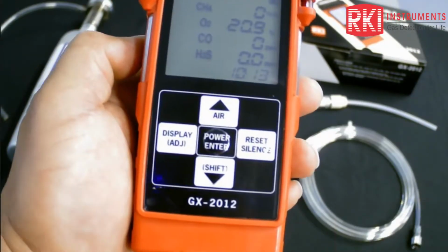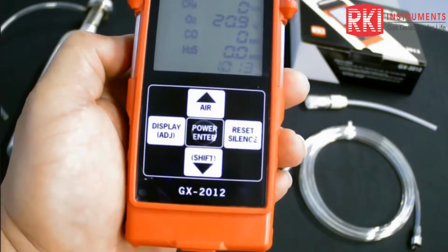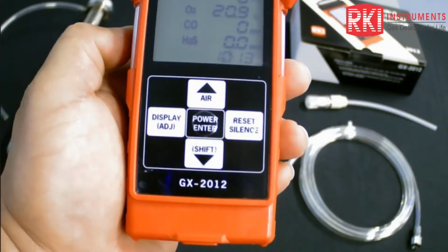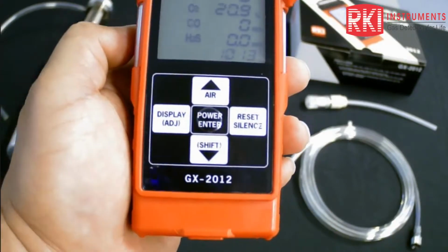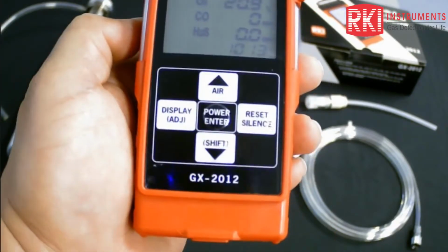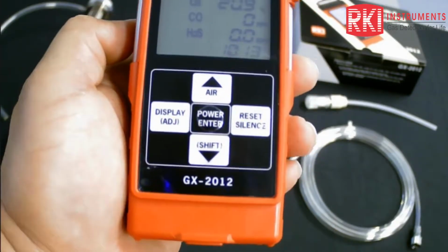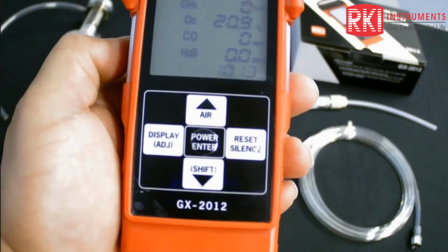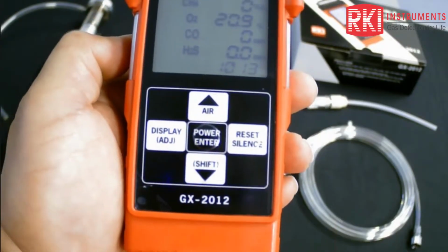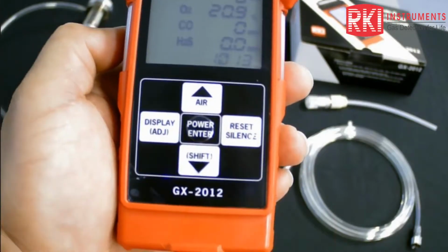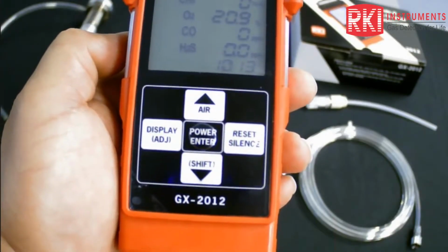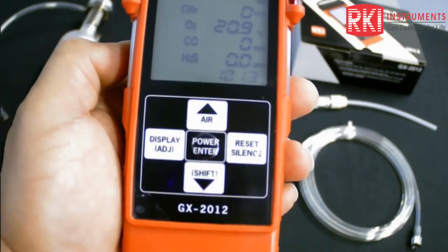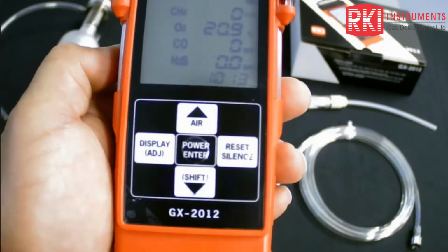So the active element has what we call a catalyst coating on it, and that's why we call it a catalytic sensor. And the purpose of that catalytic coating is to enable us to measure the gas at below LEL levels, because without that catalytic coating, you would measure the gas right at the LEL, because that's when gas will become combustible or flammable, when you have the right mixture of fuel to heat and oxygen all together.